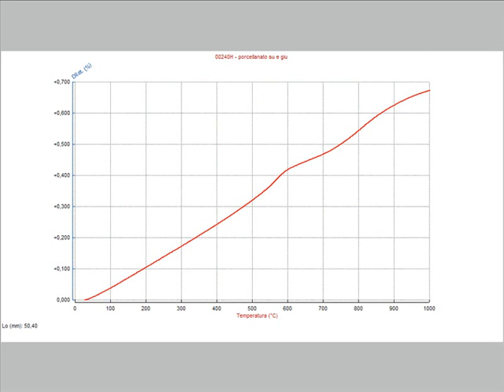This is the result of the test on a porous ceramic body. In this case, the measurement can be extended up to higher temperatures compared with traditional dilatometers. In this case, we can clearly see that the curve above the quartz transition is not quite linear, but it shows a complex behavior.